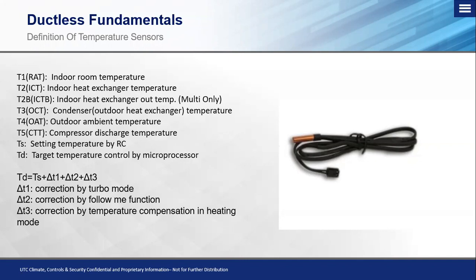So as a rule of thumb on the indoor unit, whether you're dealing with a cassette unit, a high wall unit, a ducted unit, a floor console, all true ductless indoor units have two main sensors. First one is going to be your T1 sensor, which is your return air temperature sensor, or in this case, your indoor room temperature sensing thermistor. You have your T2, which is your indoor coil temperature thermistor.